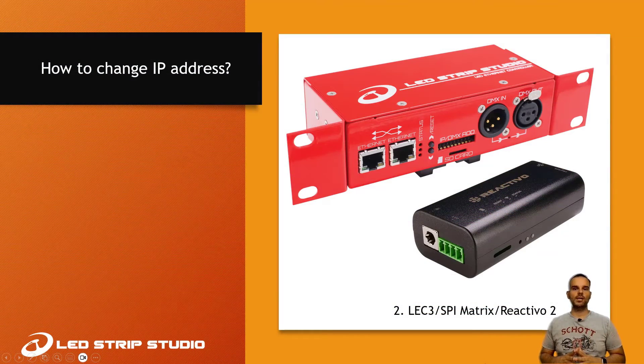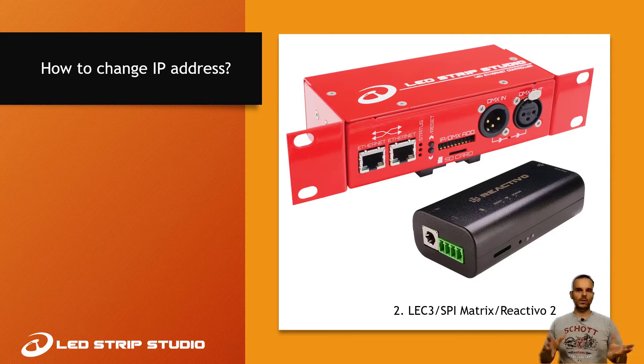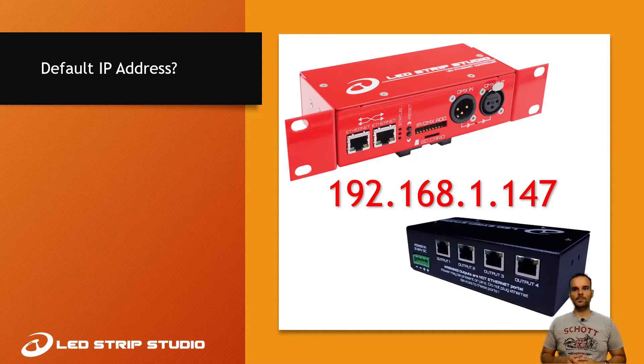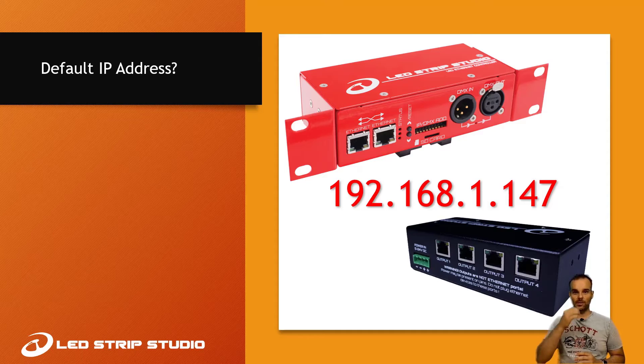Now the question is how to change the IP address of the LEC3 or SPI Matrix. There is a little help: by default, when you obtain the device, it already has the IP address set. The default IP address for LEC3 and SPI Matrix is 192.168.1.147. This is the IP address you can type into your web browser — and that's what we do now.